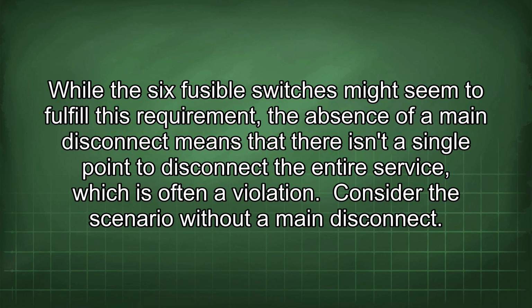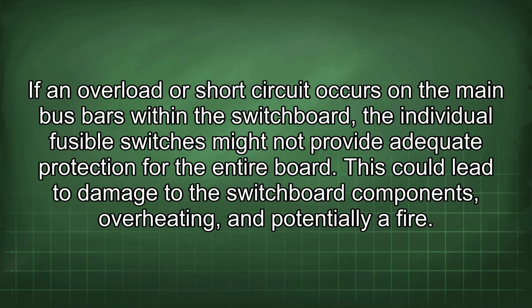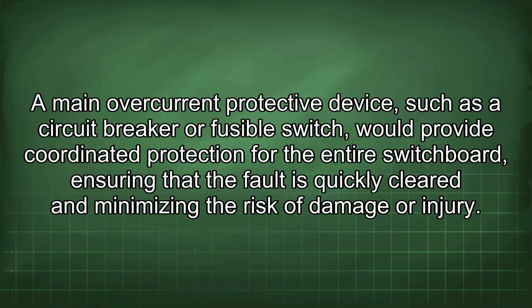Consider the scenario without a main disconnect. If an overload or short circuit occurs on the main bus bars within the switchboard, the individual fusible switches might not provide adequate protection for the entire board. This could lead to damage to the switchboard components, overheating, and potentially a fire. A main overcurrent protective device, such as a circuit breaker or fusible switch, would provide coordinated protection for the entire switchboard, ensuring that the fault is quickly cleared and minimizing the risk of damage or injury.